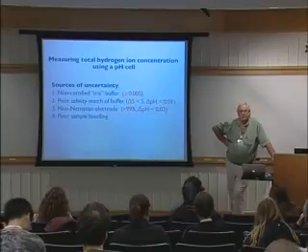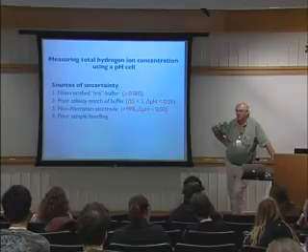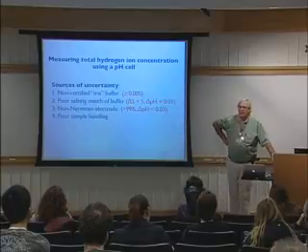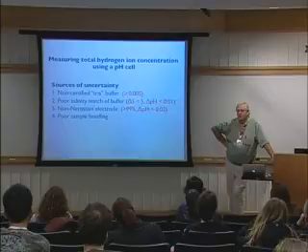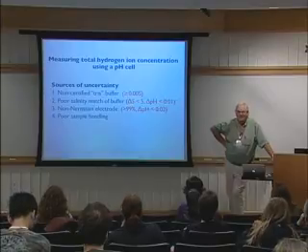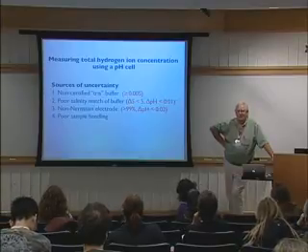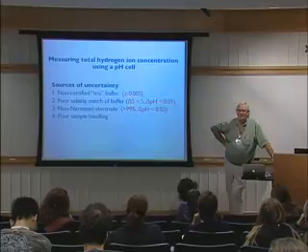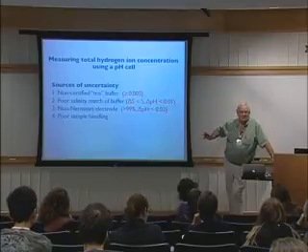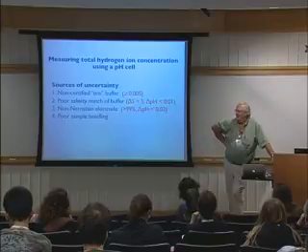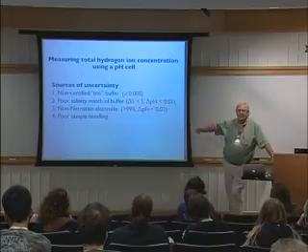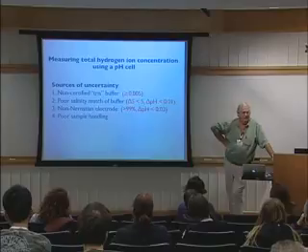Not actually as much as you would fear, because it's a logarithmic scale. 0.01 looks like a nice tiny number, but that's almost 2.5% change in hydrogen ion concentration. So 2.5% change in PCO2 is about what it corresponds to. Given that this isn't that precise, the sample handling isn't quite as demanding as you might have feared. But it's still there. You can mess it up with poor sample handling.